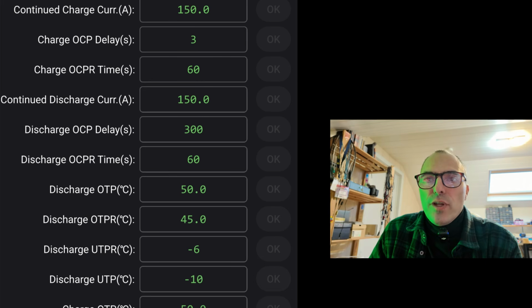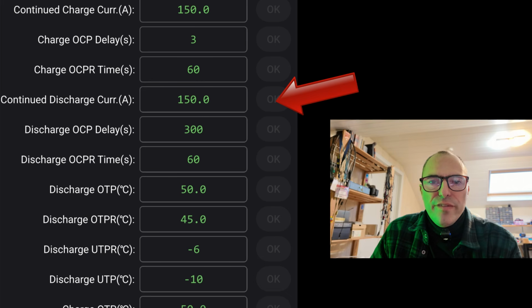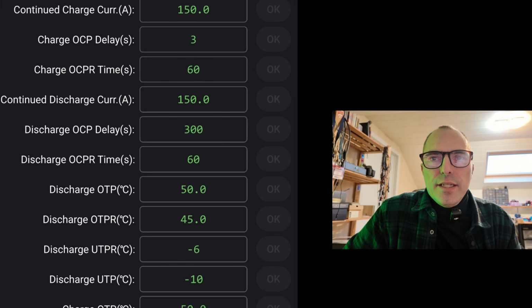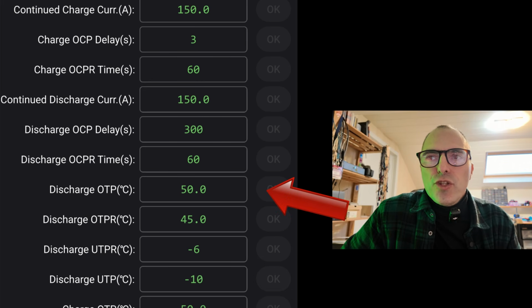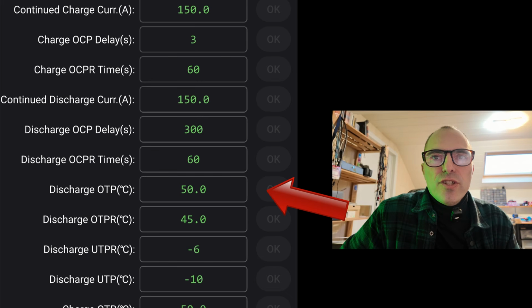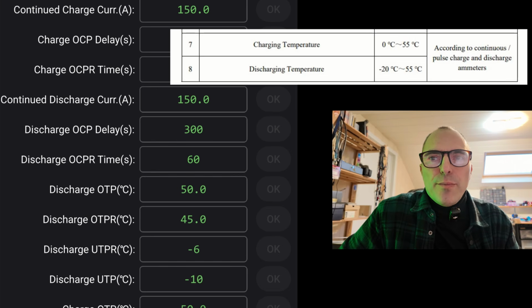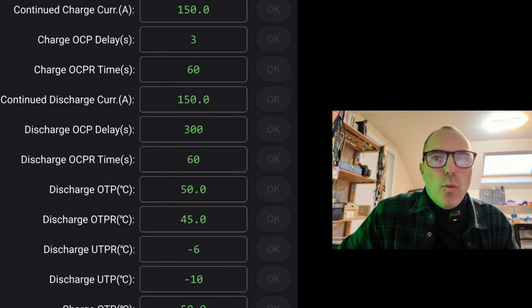Now we have the same settings for discharge: continued discharge current, discharge over current protection delay, and discharge over current protection return. I didn't change the standard values, just added a 20% safety margin and limited the discharge current to 150 amps. Charge and discharge over temperature protection and charge over temperature recovery are set to 50 and 45 degrees. These values are available in the datasheet. These temperatures are reported from the 4 temperature sensors, not the BMS module itself. If one sensor is triggered, then the BMS will disconnect the battery.